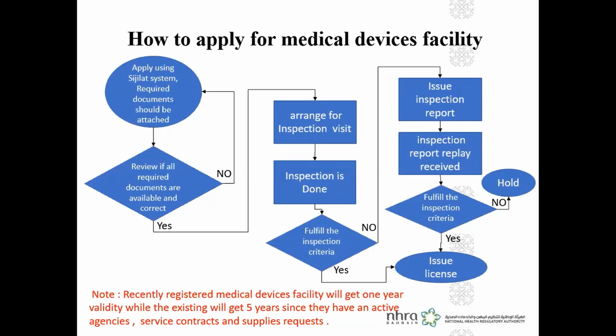If the provided documents are correct, the applicant will get the initial approval. At the same time, an inspection requirement sheet will be sent to the applicant to comply with the requirements. Then the applicant should request an inspection visit. The NHRA team will visit the facility and inspect in order to check if it complies with the provided documents and inspection requirements. If it is in compliance, the license will be issued. If it is not, an inspection report will be issued.